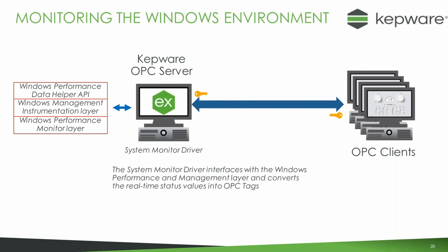It was only by installing System Monitor on the PC and monitoring the behavior of Windows that it was noticed that only when this particular operator was logged in at certain times would this error occur. We could see exactly what thread was taking all the memory, and we could then dive down and figure out what thread that was, and it turned out to be a DVD writer. That was very, very hard to diagnose otherwise. So again, a very useful way of monitoring people doing things with the server PCs they shouldn't be.